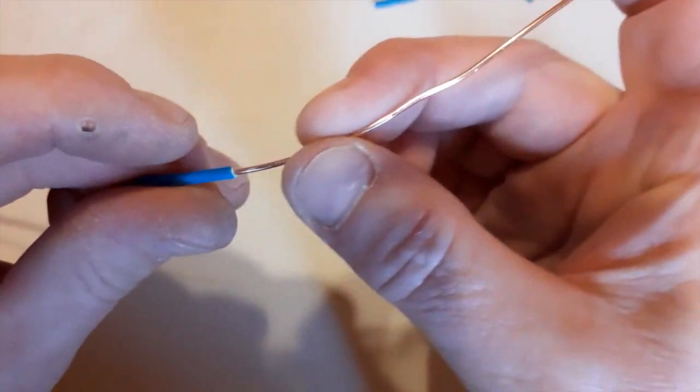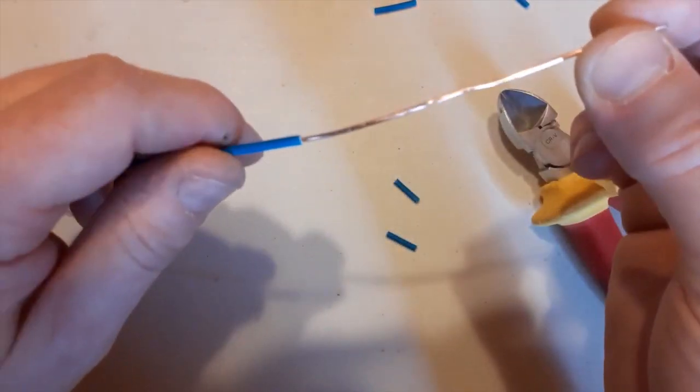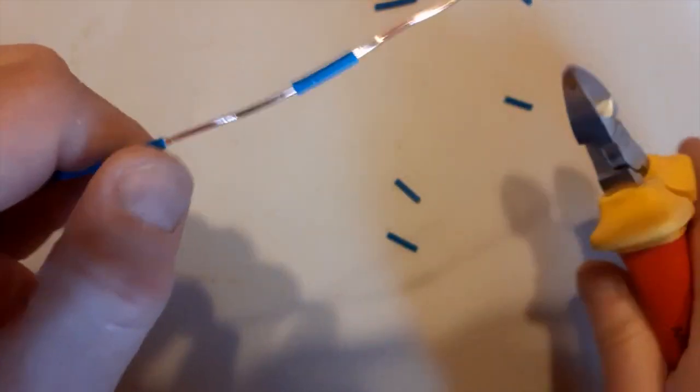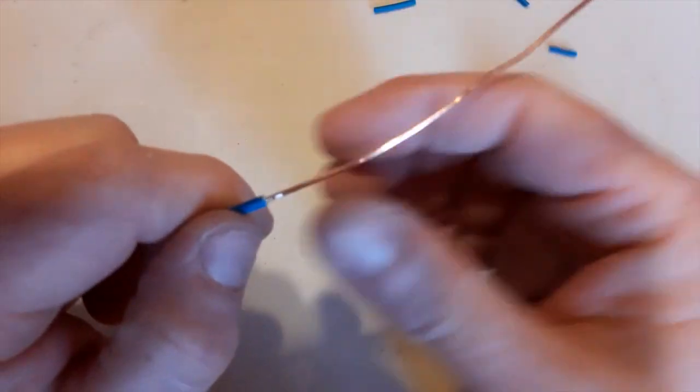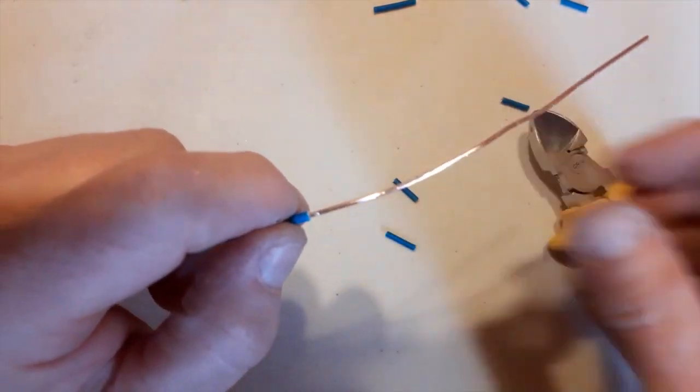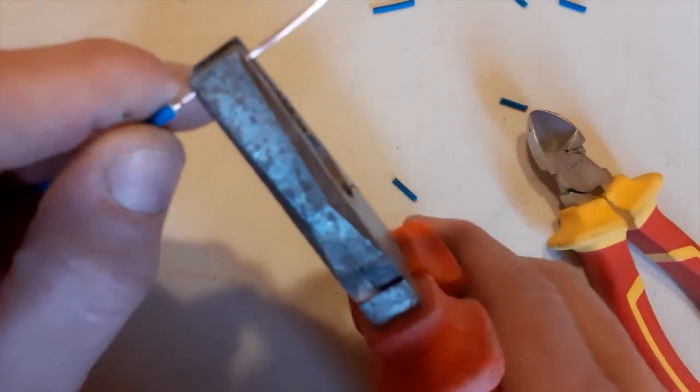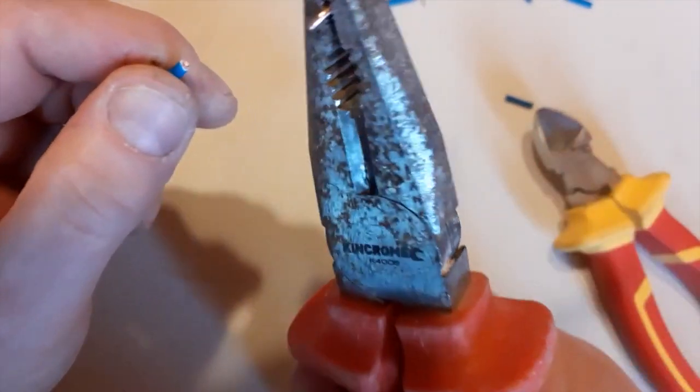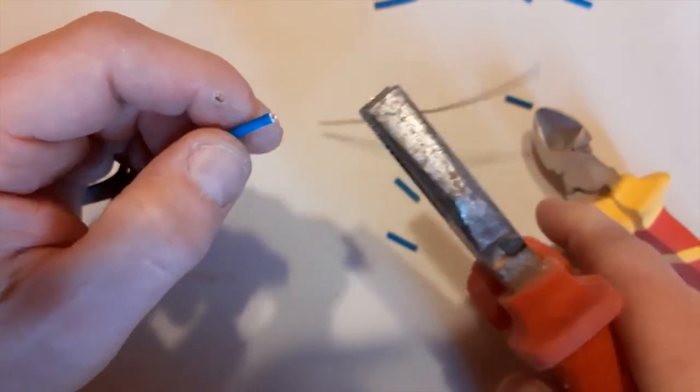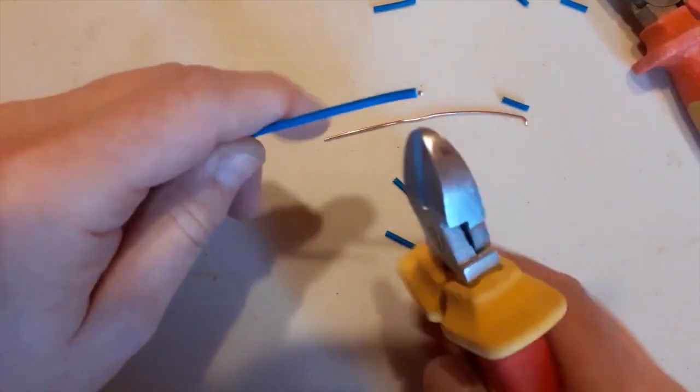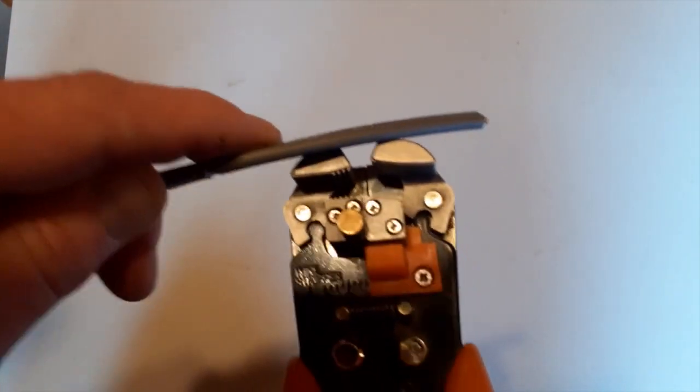But when you run your fingers up and down it, you can feel little nicks in it, and those nicks are quite a big weakness in the copper. When you bend it, it'll snap quite quickly. So let's have a go. One, two, three, four. See how quickly that snapped there because I just pressed down a little bit too hard on my snips and just scored the end of it.